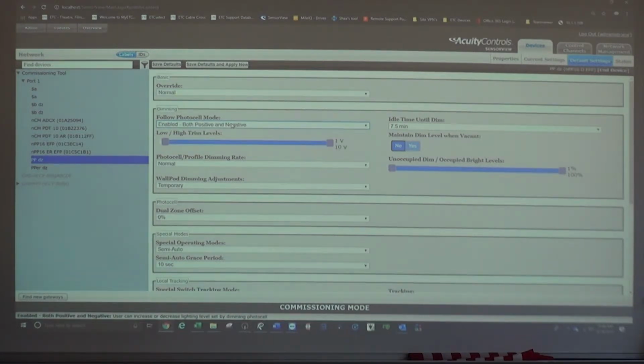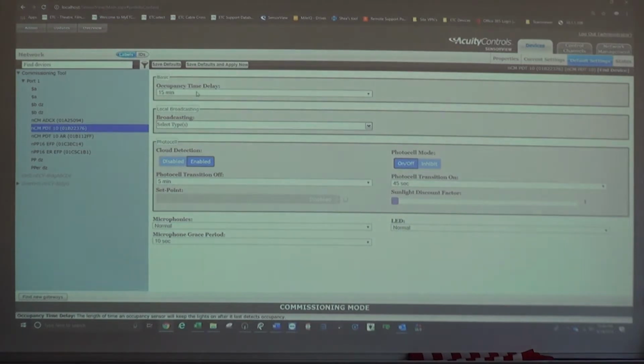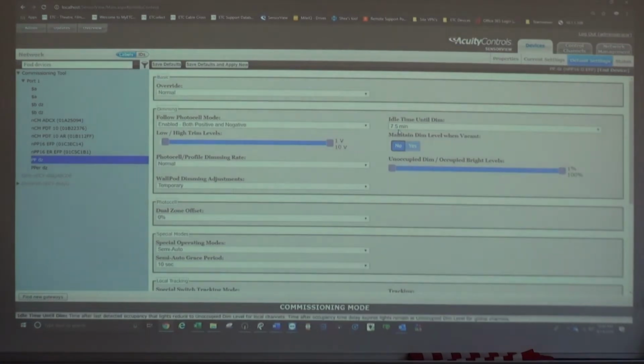You can hover over it to see what it is at the bottom — you can set... we didn't change any of those, your idle time until dim. So for this space, the occupancy sensor has an occupancy time delay of 15 minutes, and on the power side that means after 15 minutes it turns off. But there's a warning built in: at 7.5 minutes the lights go down to 1%, if it doesn't sense motion within that time, to warn the room it's about to shut off.